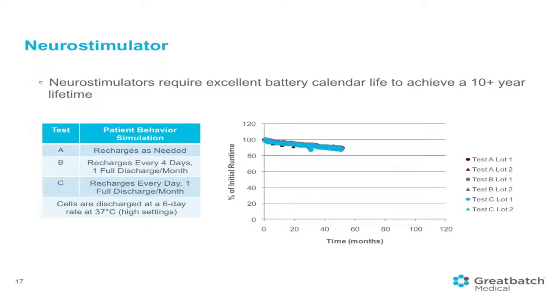But this is an example of some neurostimulator stimulation testing that we've been doing for 5 years. When you look at this particular application, this is actually a 6-day discharge. The discharge rate in a neurostimulator is very, very low, and this would actually be considered a high rate. This is like the highest that you might see. More typical might be a month or 2 months. So very few cycles over the course of 10 years. But in this particular case, we're trying to stress the battery by going with a 6-day rate.